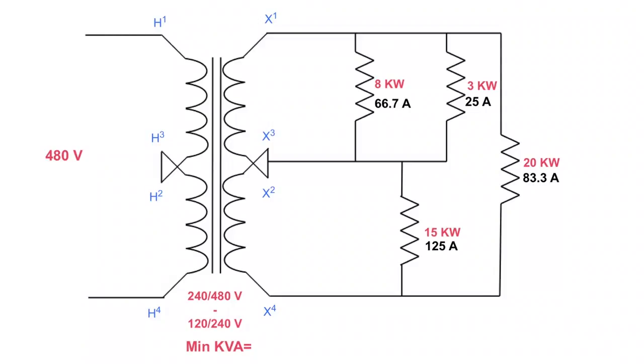Now we've determined all the current going through each branch, we can determine what our line currents are going to be. Line one: all I have to do is take 66.7 plus 25 plus 83.3, which gives us 175 amps on this line. Then going to line two, we take 83.3 amps and add it to 125 amps and we get 208.3 amps.